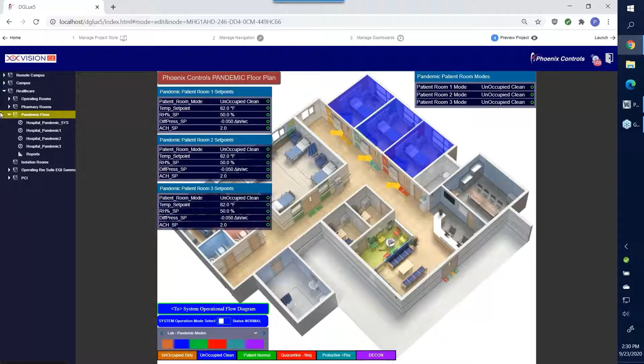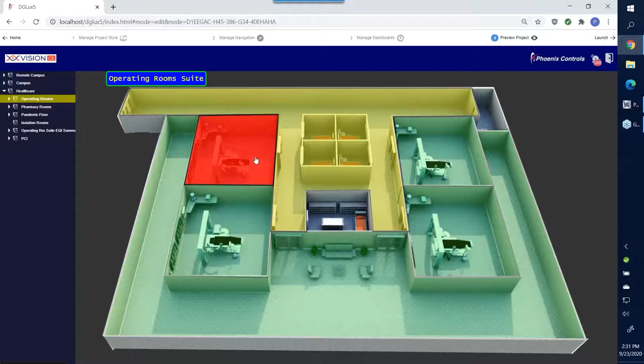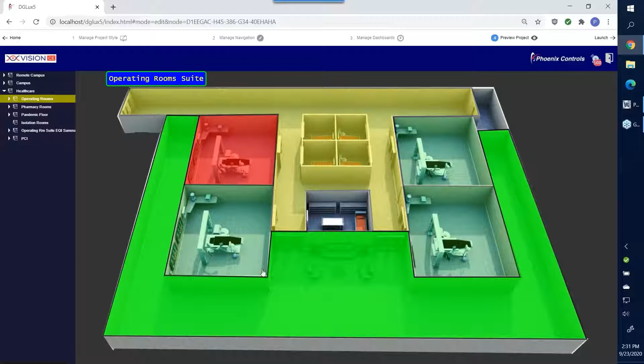Again, the idea would be we create a very simple approach for the nurses to know that there's a parameter within the operating room, and these suites are typically built out in multiple arrangements from 4 to 6 to 8, but that the end user or the nurse on staff would be looking at these rooms, and if there's a problem, they could either just stop here, call facilities and say there's a parameter that we have a problem with, or they could jump into the room itself to get a range of information associated with the room's operation.